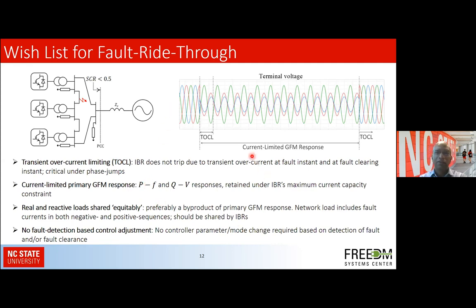And not only at the fault instant. This graph shows that when you're entering the fault mode, oh, okay, the cursor is moving by itself. Anyway, when it's entering the fault mode, there will be an overcurrent depending on the operating condition. And again, there will be an operating point when overcurrent is possible when the inverter is coming out of that fault mode and going back into normal operation. So under both of these, the transient overcurrent trip should not occur, for the IBR to keep continuing to provide support to the grid. And also the current-limited primary GFM response, which is the real power-frequency and the reactive power-voltage responses, should be retained under the constraints of the IBR's maximum current capacity.